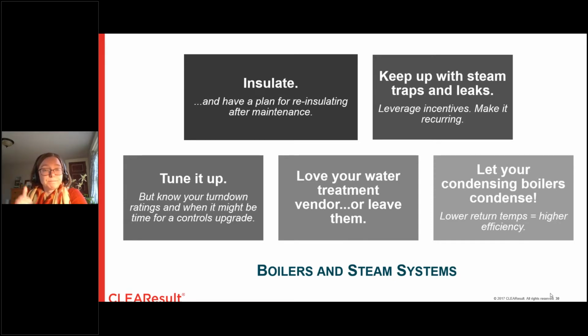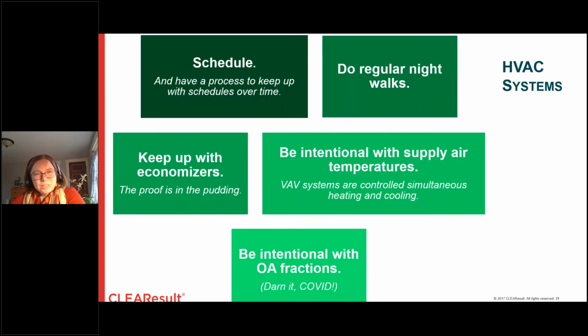Tune-ups are amazing. And then I'm going to say water treatment again. Just like a dirty cooling tower doesn't exchange heat well, dirty boilers don't exchange heat well. So love your water treatment vendor or ditch them and get a new one. And then let your condensing boilers condense.